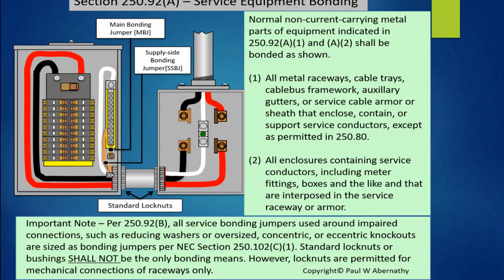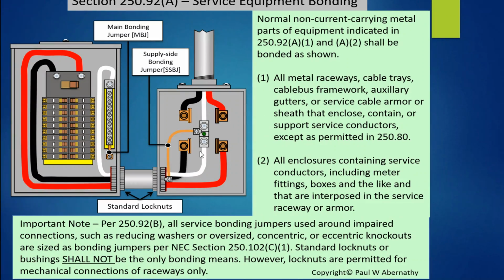Okay, so in this case, we're going to assume that it has rings that had to be knocked out, and there's still a couple of rings left in there. So here they use the bonding bushing, and it's mechanically held by the lock nuts, standard lock nuts for mechanical purposes, and that's why he had to put a bonding jumper here. Now, it could have been done over here, but it was done over here. It doesn't matter which side. The only problem over here, and we'll show that in this graphic, is that many jurisdictions don't like this because they say that when the inspector comes, it's not accessible. The other thing is, it's so vital that this piece of raceway doesn't become an island that it has to have this supply side bonding jumper.